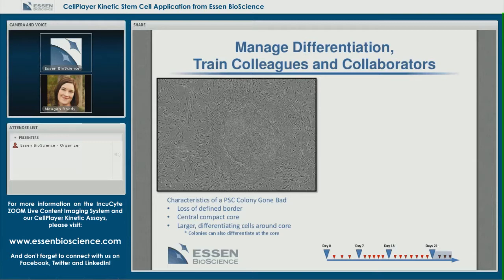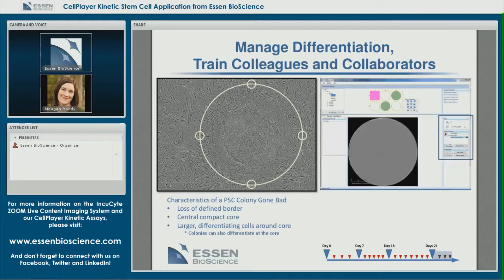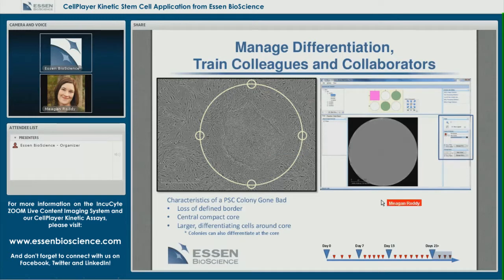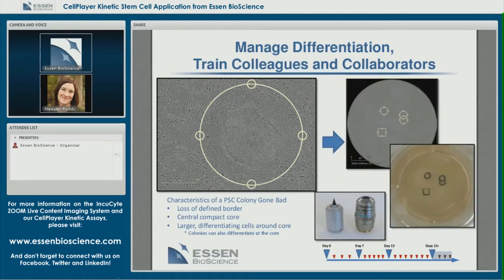What does the researcher do at this point? We're either going to want to clean the differentiation or remove the colony altogether. If there are only a few colonies with evidence of differentiation, the researcher can choose to clean away the differentiated cells, or physically remove the whole colony to cleanly dispose of undesirable cells. Using the printing mark tool, you can digitally place a circle or square around the colony of interest, then remove your objective, put in the IncuCyte marking tool, hit print, and those digital marks will be printed onto the actual well or dish. You then replace your objective, take your plate out, and perform the manual work.